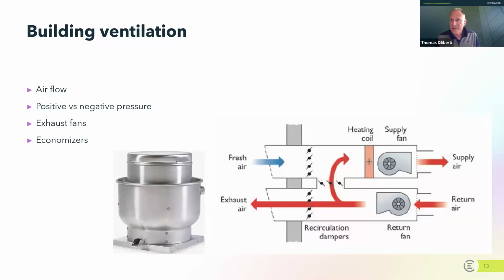Again, we're going to talk about several different types of air handling units shortly. And you'll see there are lots of different words and lots of different terminology, but in general, this is the general flow of air through a building. So let's talk about positive and negative pressure. Buildings can and should be positively pressured. They should be slightly positively pressured. And what I mean by that is the air coming in from the outside: there should be a little bit more air flowing into a building than air flowing out of a building. A little bit more air flowing in than flowing out keeps the building positively pressurized, and it doesn't allow air to creep in through spaces where you don't want it to.